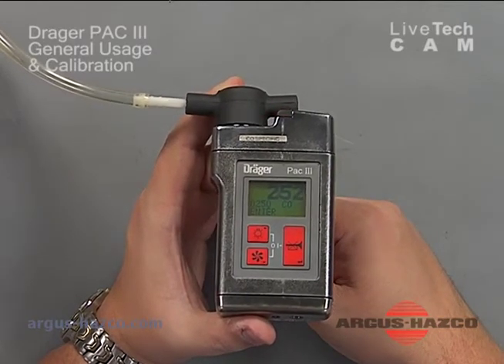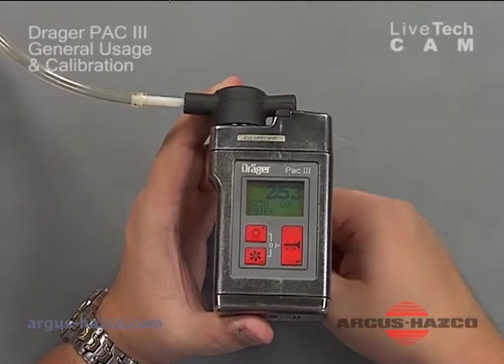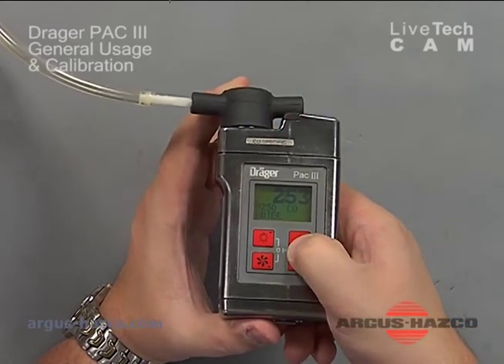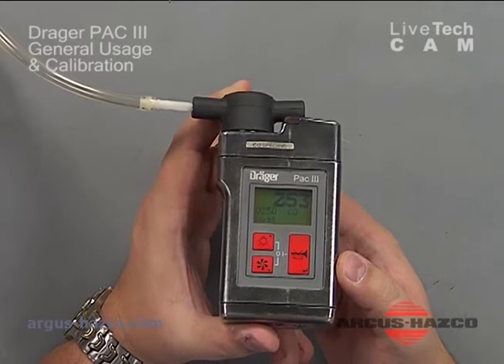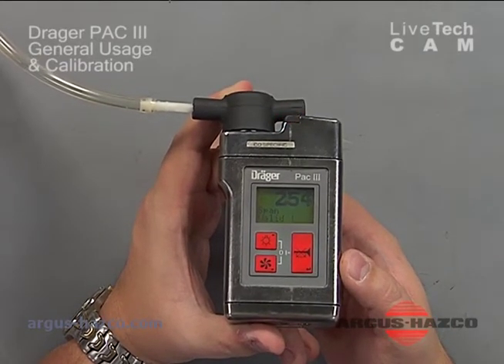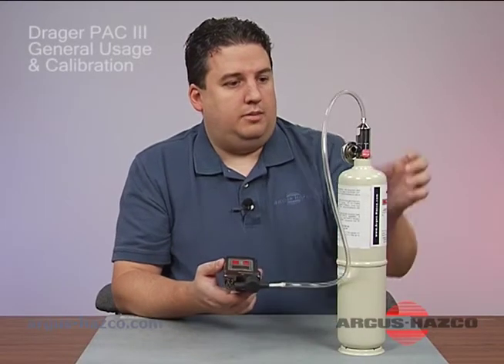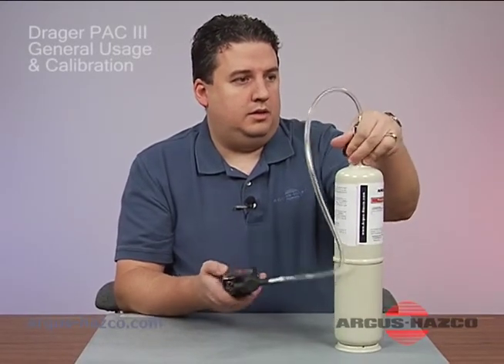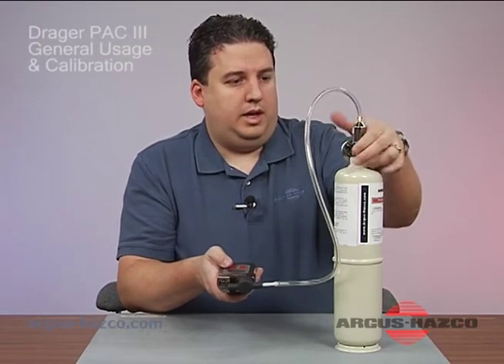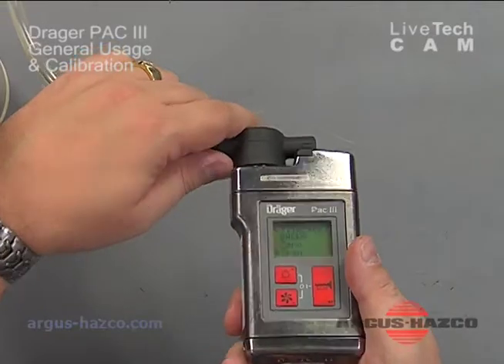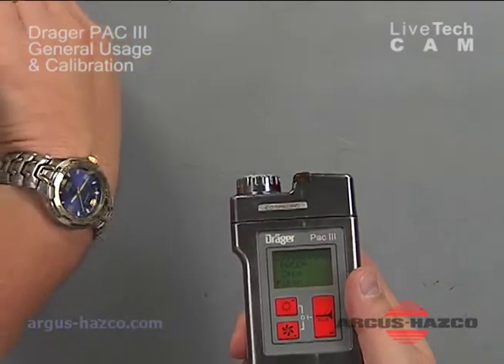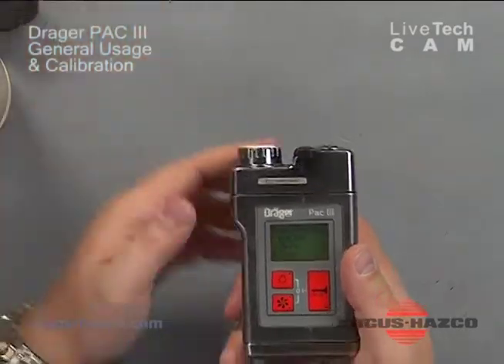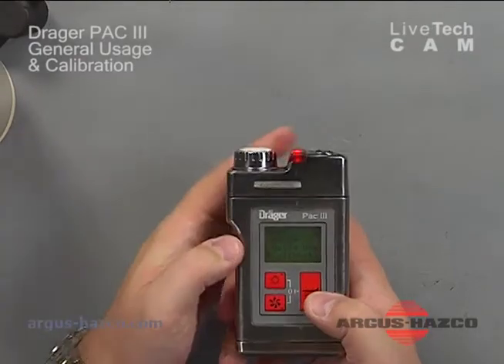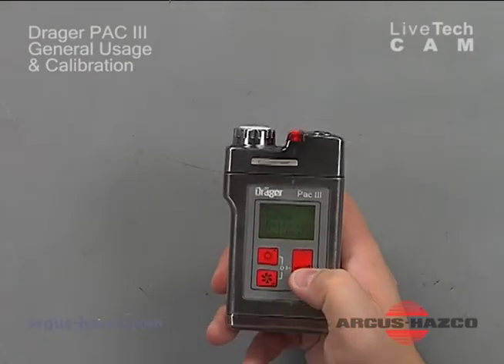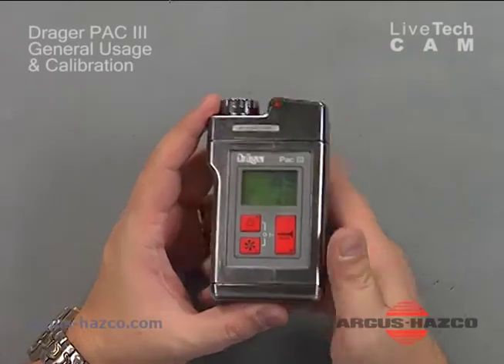After about 30 seconds or so, if the reading's somewhat stable around 1 to 2 ppm, you can go ahead and press your enter button. When you press your enter button, it'll say wait, span valid. At that point, you can go ahead and turn off your calibration gas, hit your enter button, takes you back, and you'll hear it go into alarm because now you're not in the span calibration mode where it nullifies the relay for the alarm. If you go to your back button, go back, you'll see that it's in alarm condition right now.